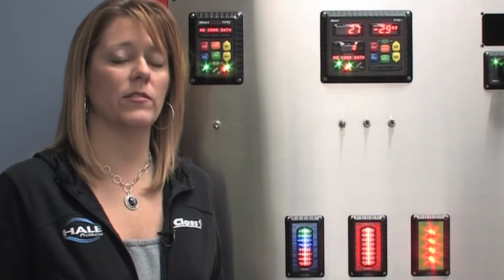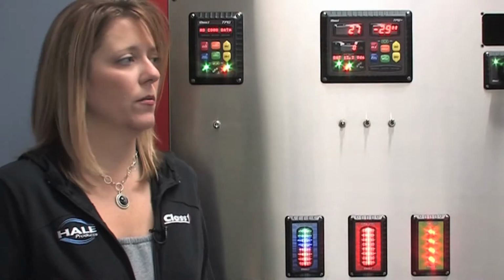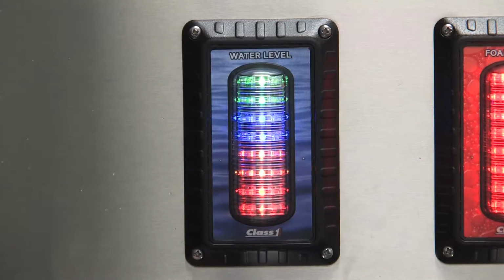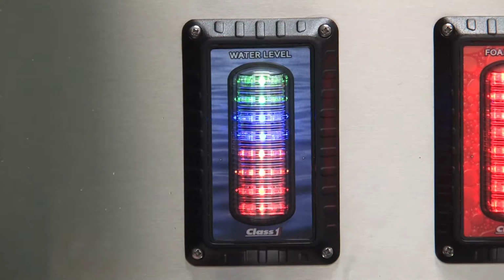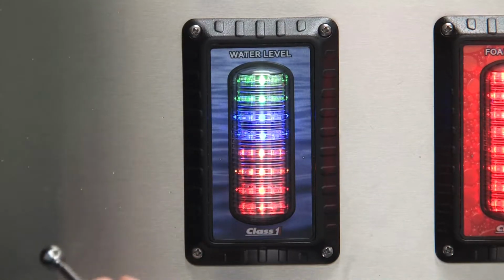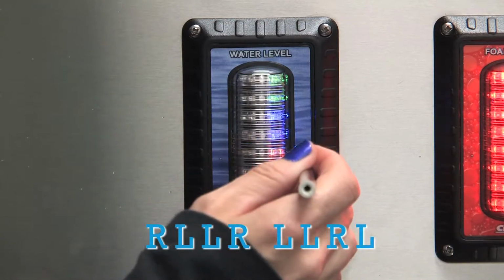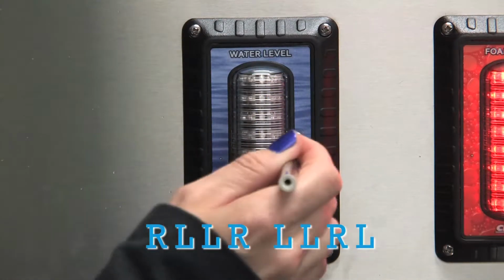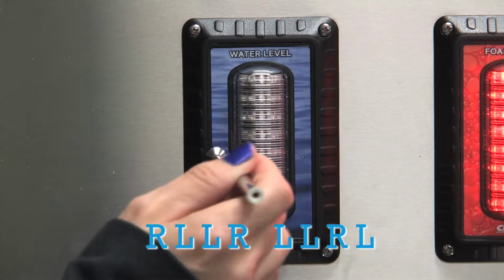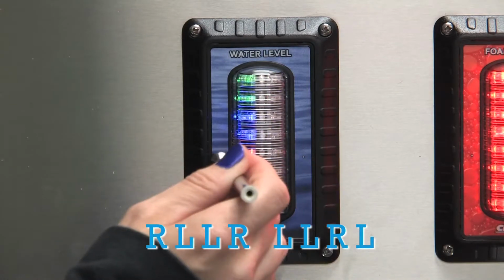A 2-point calibration is the most common method to calibrate your ITL40. You can start with either an empty tank and then fill it, or you can start with a full tank and then empty it. We're going to start with an empty tank first. To calibrate a 2-point calibration with an empty water tank going to a full water tank, we're going to do the calibration sequence right, left, left, right, left, left, right, left.